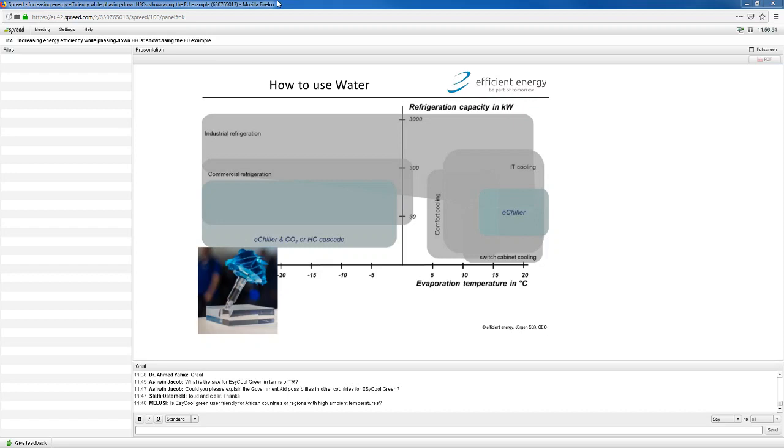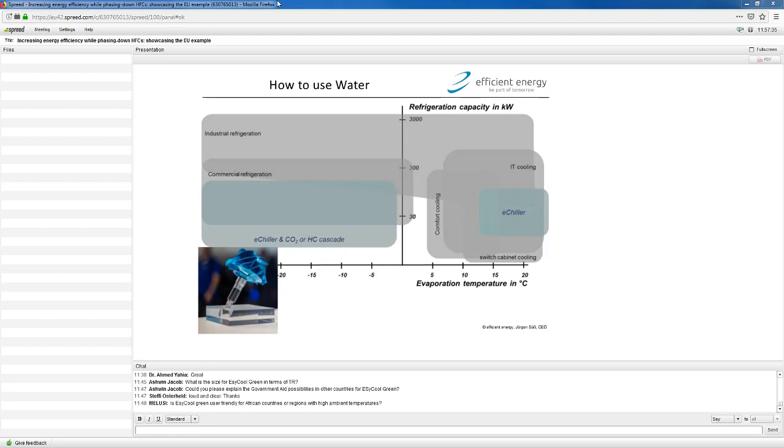If we use, for example, a CO2 system, and we have heard that in the presentation before, the efficiency goes down if the temperature outside goes up. If we put a cascade together with water, up to 100 degrees C everything is in vacuum anyway, so hot climates are no worry. We can definitely—I mean, this machine never goes on a high pressure failure wherever we are on this globe or the earth. This means we can give Norwegian climate to the entire world, and the CO2 system standing somewhere in the Middle East would just say, well, it's just standing in Norway. So that's a very, very interesting combination of two natural refrigerants, CO2 and water.